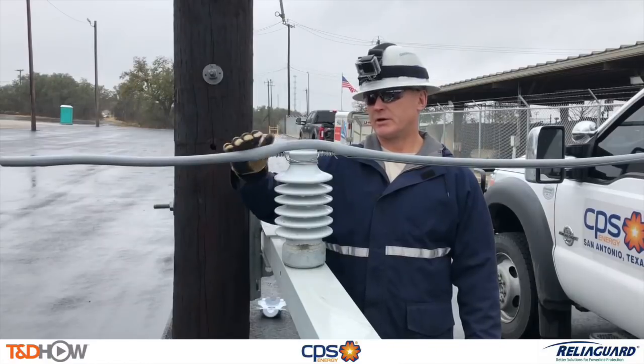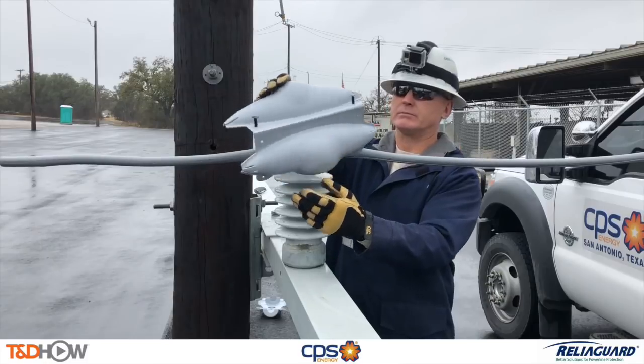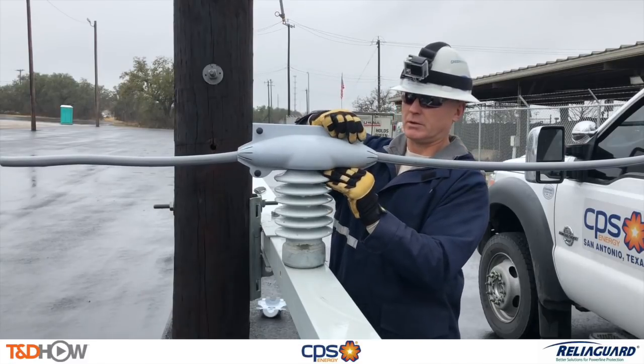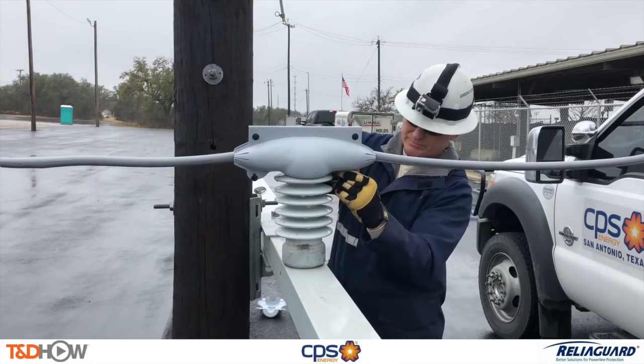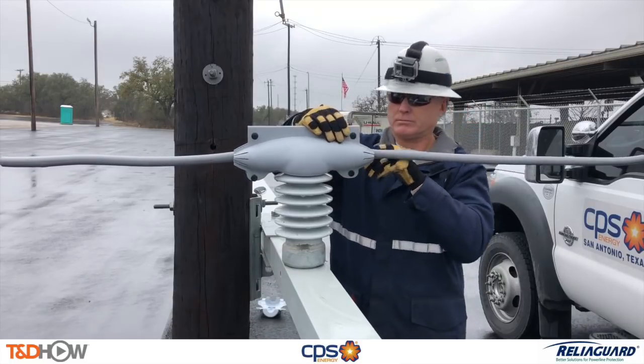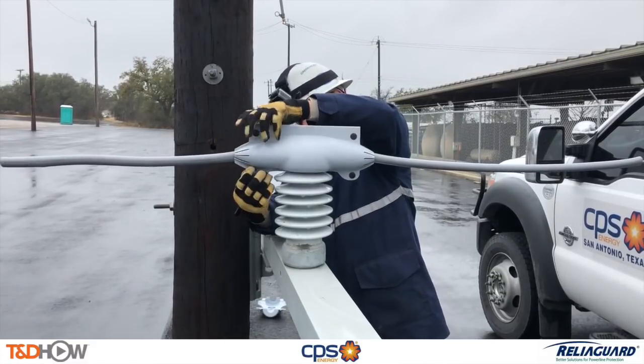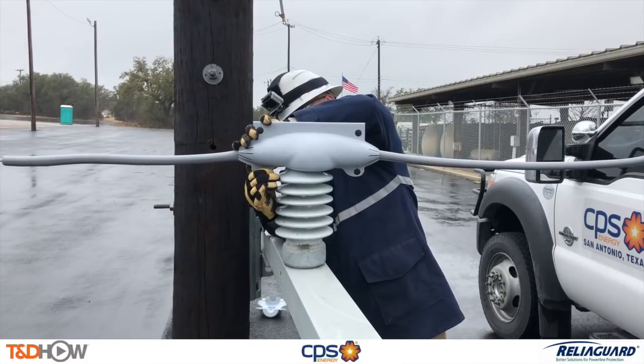Next we will see Marty install a pin insulator cover. In this case, note that the gray eel conductor cover has been installed in one continuous length rather than one on each side of the insulator, in order to prevent migration over time. The black pin fasteners are easily attached while wearing lineman's gloves. This points out that all of these products are developed with significant input from former and current line workers, providing valuable product development feedback that ReliaGuard can then use.